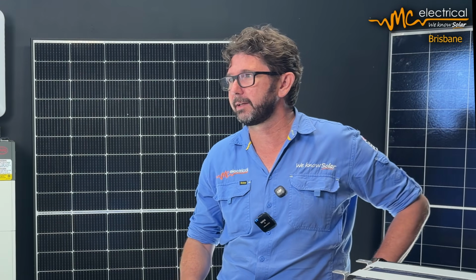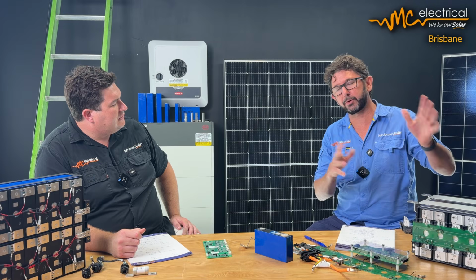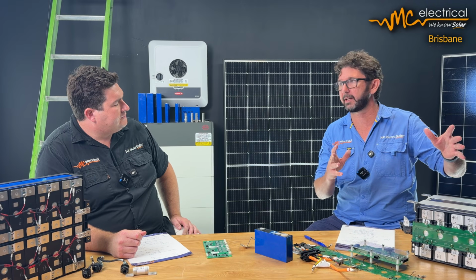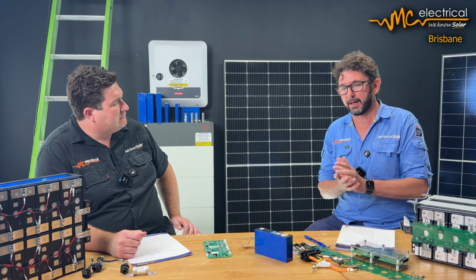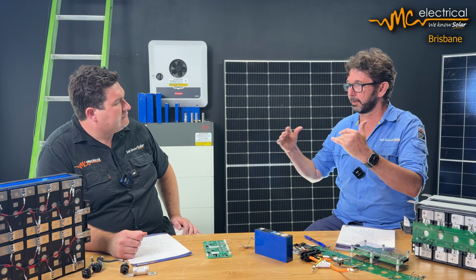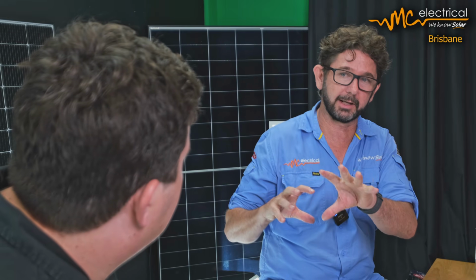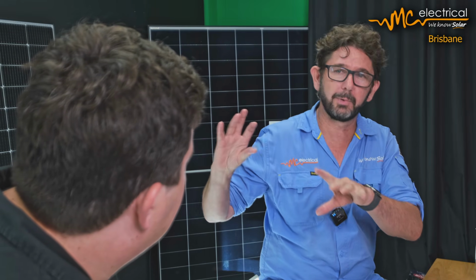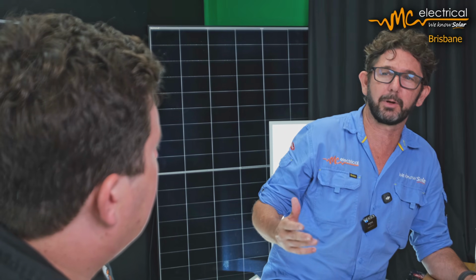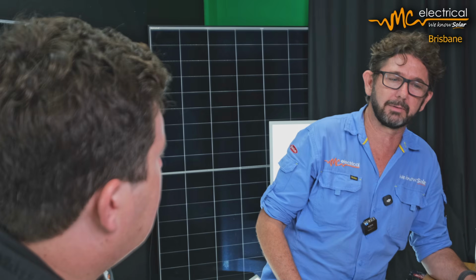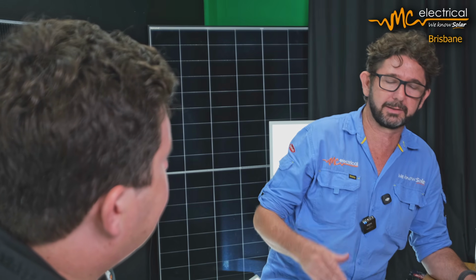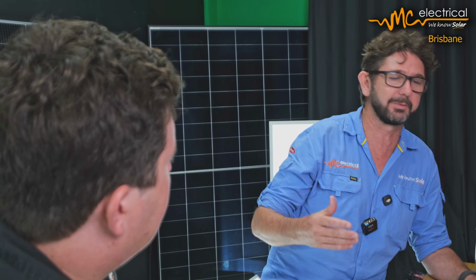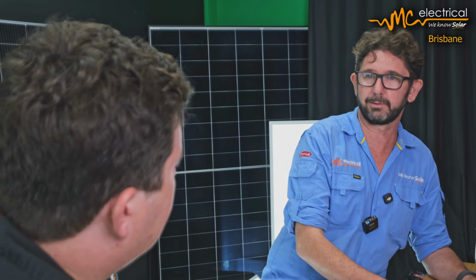We did some testing on the MPPT by throwing some cardboard over some panels to simulate shade coming over, then taking it off. We had two different arrays doing this, and compared it to the Fronius inverter at exactly the same time. It really just tripped up the SAJ inverter - it doesn't respond as quickly, it's just very slow to react. Which, to be fair, isn't unusual with cheaper inverters, but it just doesn't have as good a response to dynamic changes in weather conditions.